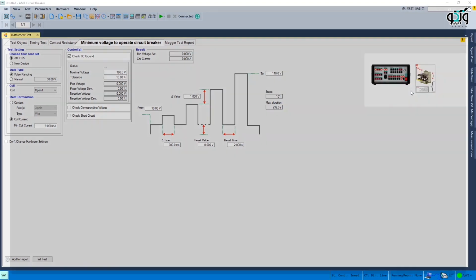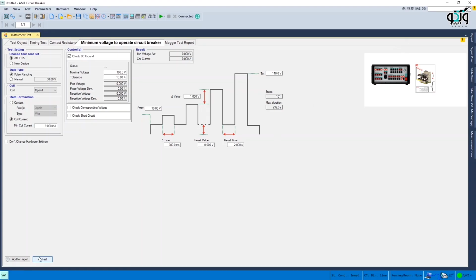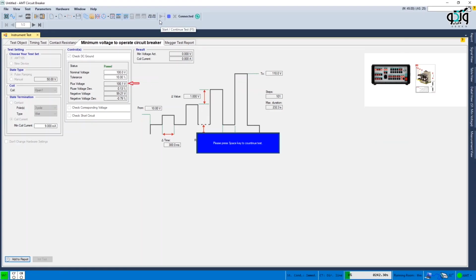To do this test, you need to specify the nominal voltage and maximum allowed tolerance after checking Check DC Ground. Here, 100 volts and 10% are entered in the required fields, and then the wiring is adjusted in accordance with the figure. After pressing Init Test and running the test, the positive potential and its difference with the nominal voltage, as well as the negative potential and its difference with the nominal voltage, are displayed.